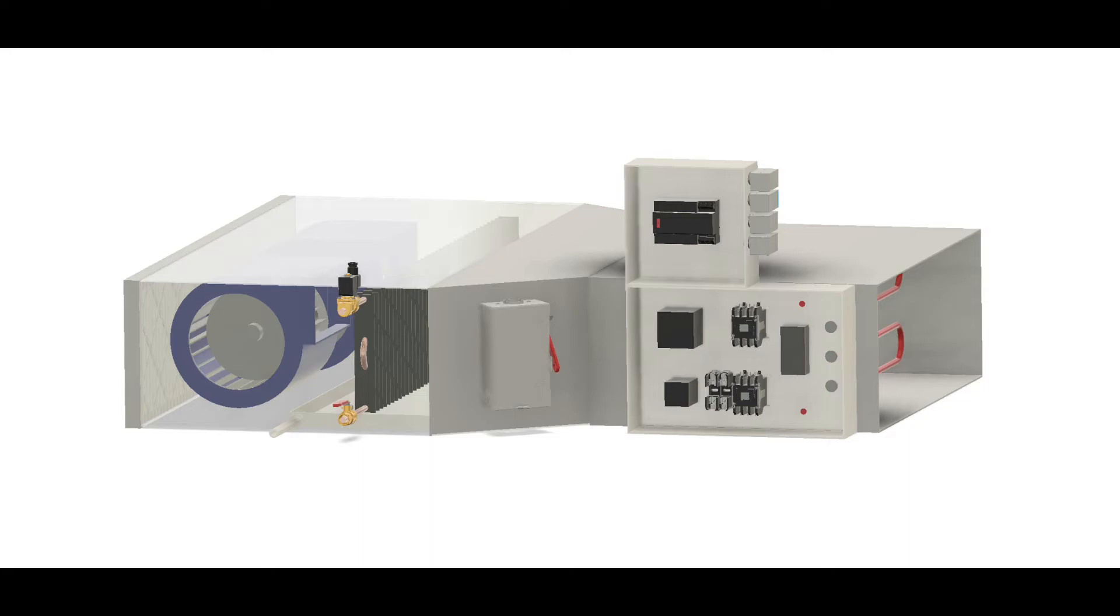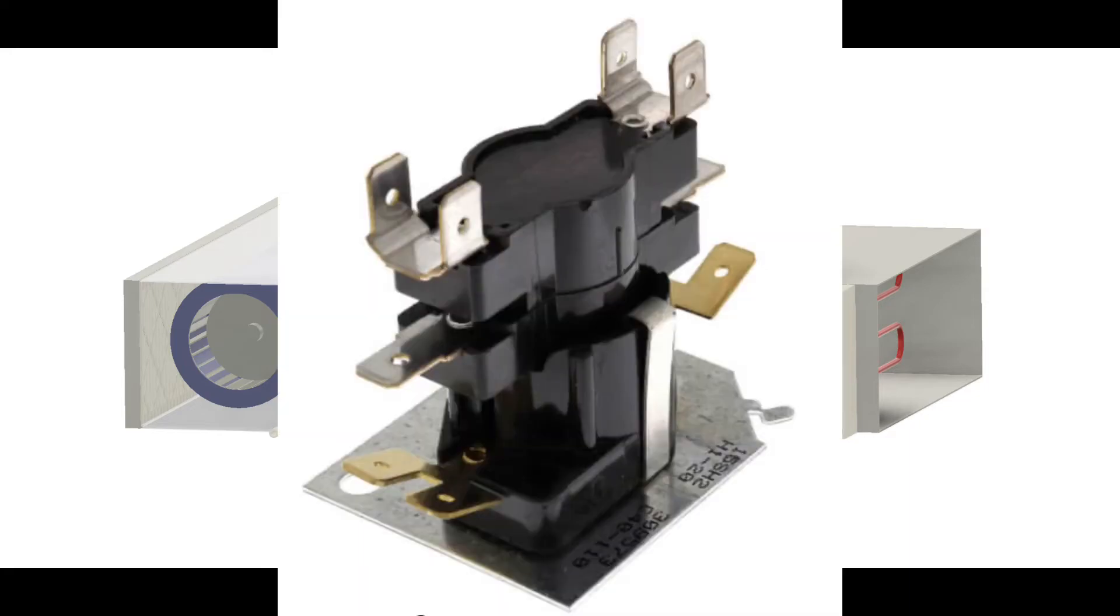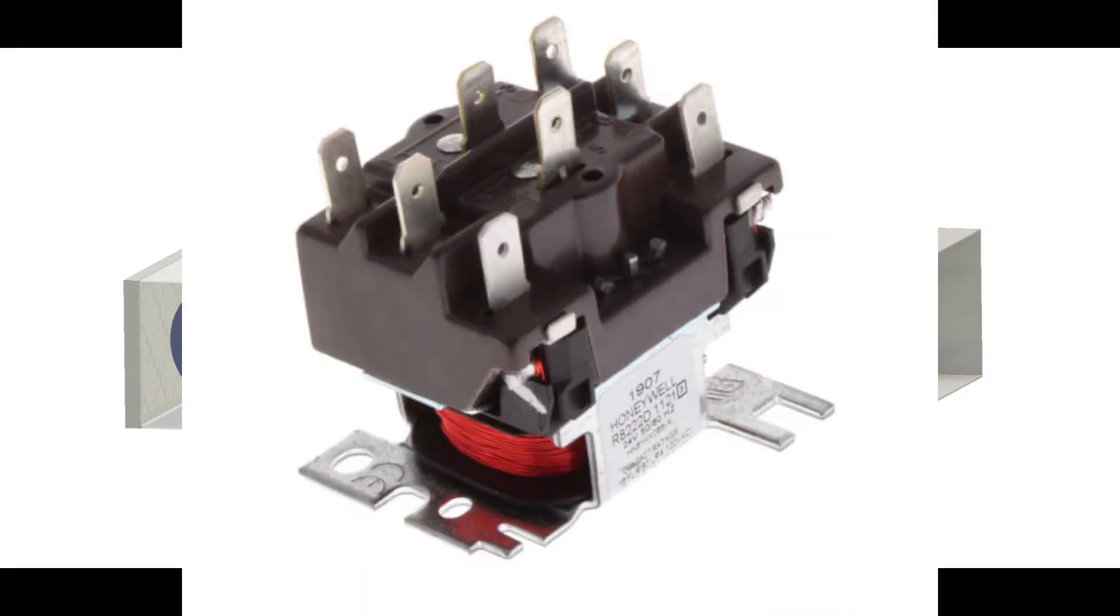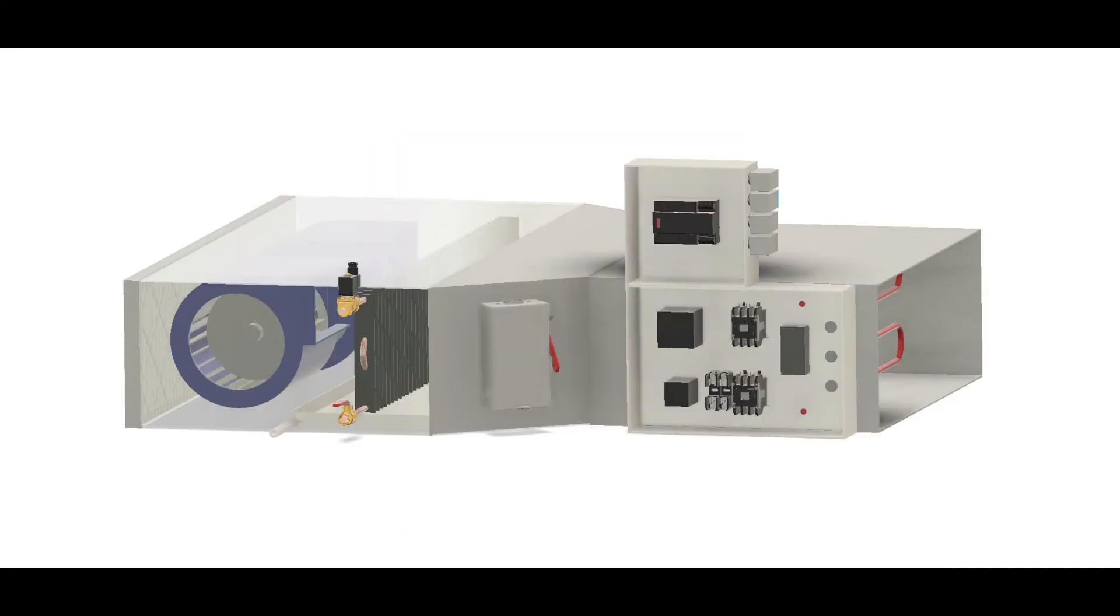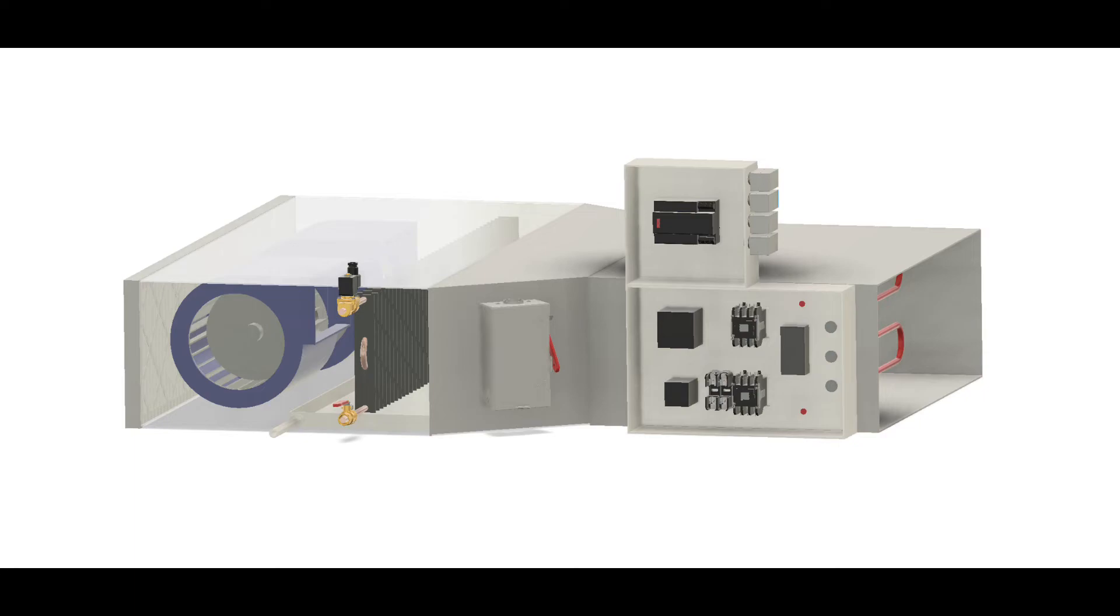If you don't have contactors on your electric heaters, you may have heater sequencers or a general purpose relay or relays that look like this. Again, same rule applies. You've got power coming in, power going out. On your coil, are you getting your 24 volts or 120 volts in and out of the coil to energize the contactor?